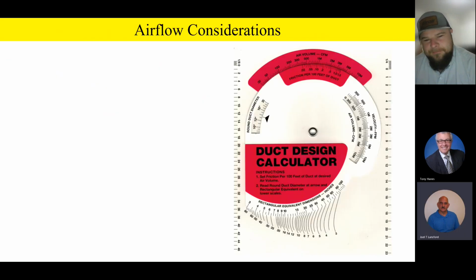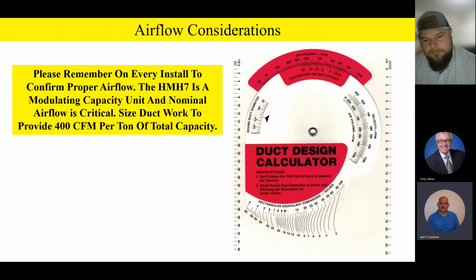Finally, one other thing we always want to make very, very sure that we stress whenever we're talking to our contractors is please remember on every install to confirm proper airflow. Now, remember the HMH7 is a modulating unit and nominal airflow is going to be critical. So be sure and size that ductwork to provide 400 CFM per ton of cooling capacity. And that's just good practice anyway for your duct sizing. But let's make sure we've got properly sized ductwork on these HMH7s for them to work properly.